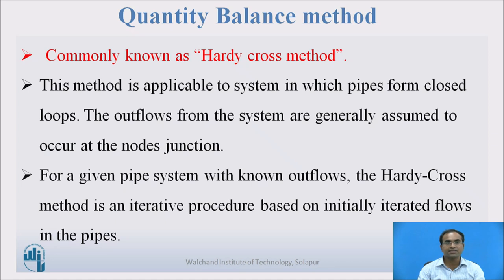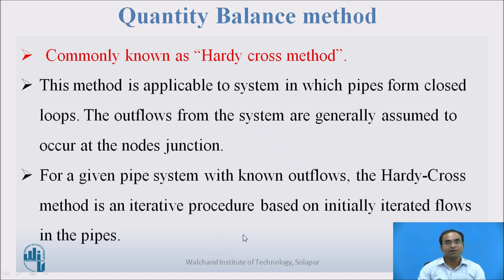The Quantity Balance Method is generally known as the Hardy Cross Method. This method is applicable to systems in which pipes form closed loops. The outflows from the system are generally assumed to occur at node junctions. For a given pipe system with known outflows, the Hardy Cross method is an iterative procedure — a trial and error method — which is based on initially assumed flows in the pipes.